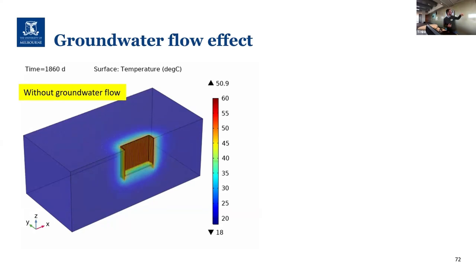Here you can see the shaft, the station box that we modeled over time, 40 meters in depth, and you're accumulating heat over here. This is a 30-year simulation, and it becomes not feasible. After 10 years in this case, the ground heats up so much that it becomes less efficient than the alternative. Not good.